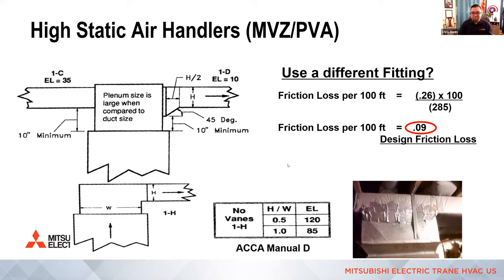All right. So just back to the presentation, just so we can keep on time here. You can see here, if I used a bullhead tee, which is a 120 foot fitting instead of a 10 foot fitting, instead of 275 equivalent feet, now it's up to 285. And when we do this math, we have a friction loss that's perfect for design, right in the middle of the minimum and maximum for design friction loss. So this duct system would actually do better with a bullhead tee, because it would be less noisy, and the velocity will actually be better in the supply if you do it this way. It's not going to be cranking, because the duct system would be too small. Okay. So sometimes a bullhead tee is good.